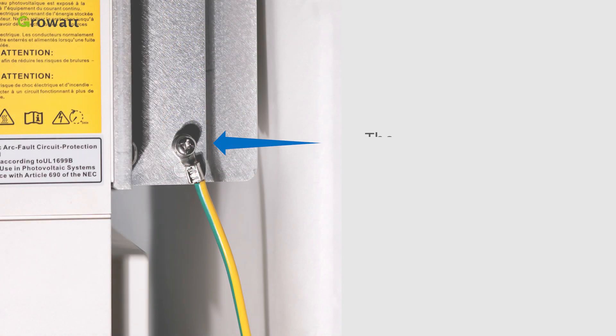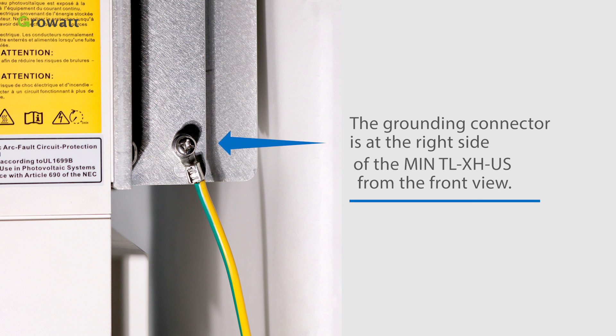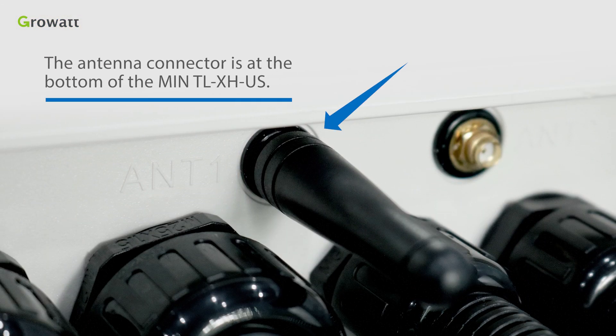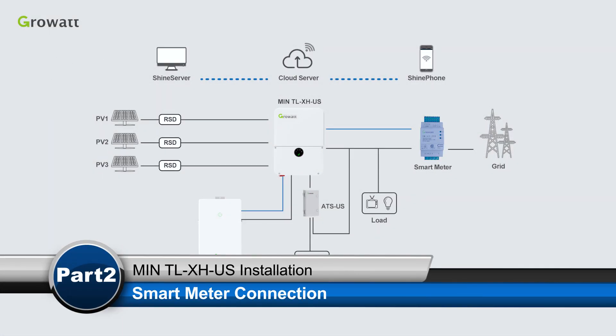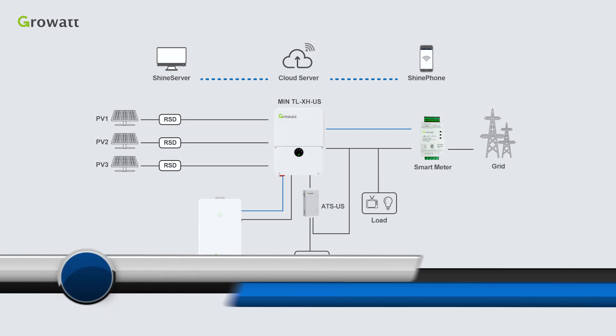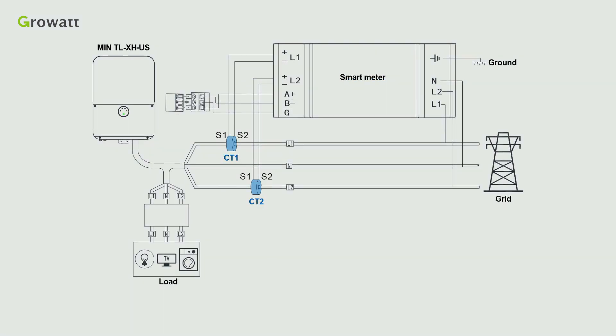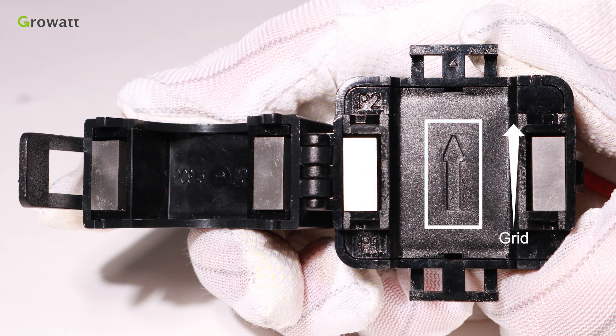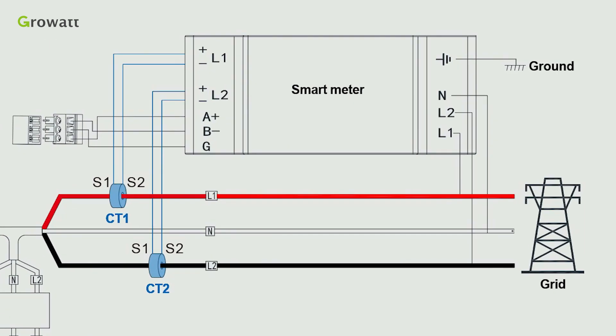The grounding connector is on the right side of the MIN TL-XH-US from the front view. The antenna connector is at the bottom. Install the CT on the power cable between the load and the grid. Pay attention to the direction of the CT — open the current transformer and you will see an arrow labeled on it, which indicates the current direction from the public grid to the user load.